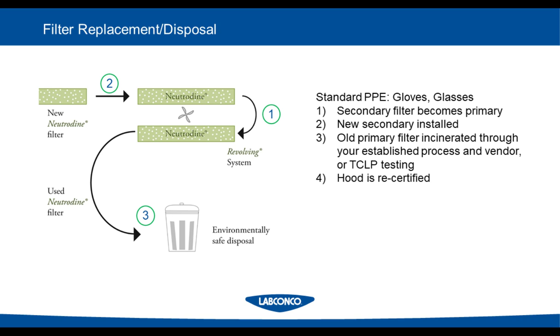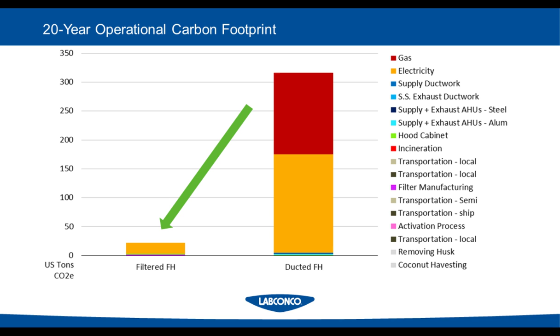When you look at the absolute best benefit of using filtered fume hoods, it's the 20-year operational carbon footprint, a 94% reduction. Many thanks to BR+A consulting engineers in Boston for the research here, looking at everything from transporting the carbon, making the filters, incinerating everything afterward, to the metal work that goes into a ducted hood versus a filtered hood—same metal cabinets, same Labconco structure—but avoiding most of the electricity cost and all of the gas cost if you're in a zone that needs to reheat. You'll see a very large reduction in carbon footprint. So when it's safe for your application, and each application must be approved ahead of time, there's a tremendous environmental and monetary benefit to using the filtered fume hood.